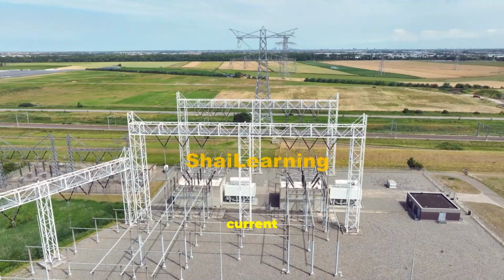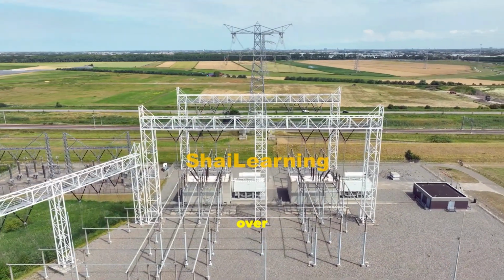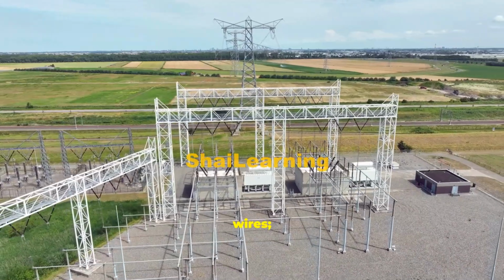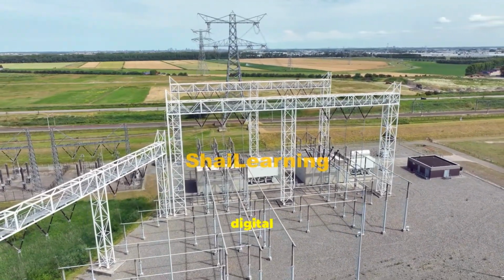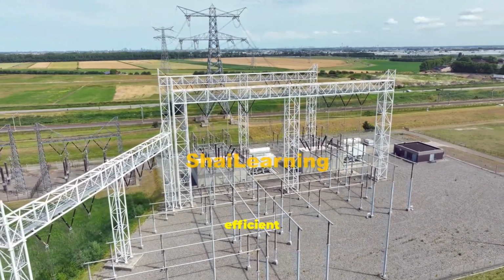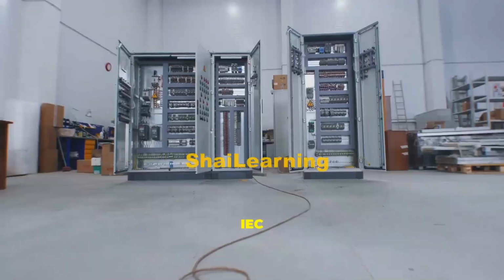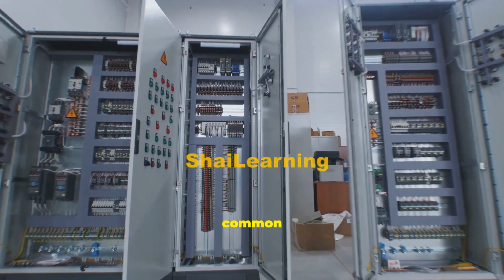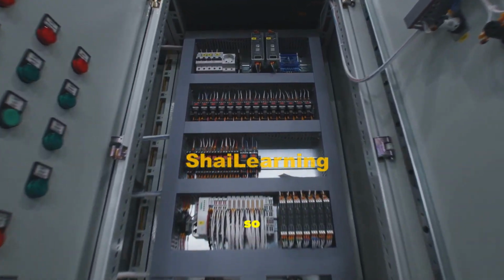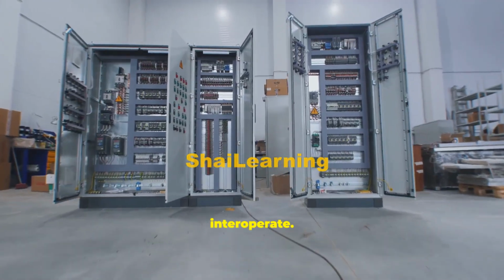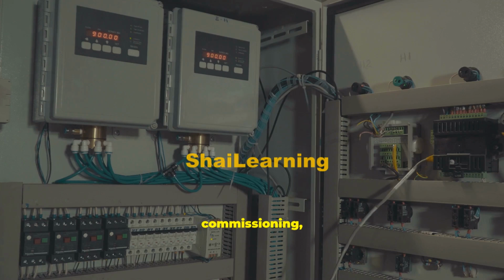Traditional substations carry current and voltage signals and control commands over thousands of copper wires. Digital substations convert analog to digital at the yard and use fiber or other efficient communication means. IEC 61850 defines a common language for intelligent electronic devices so multi-vendor gear can interoperate. This simplifies design, commissioning, and future upgrades. Digital substations provide richer data for better remote monitoring and faster fault analysis. Automation can reconfigure the grid to restore power, reducing outage times.